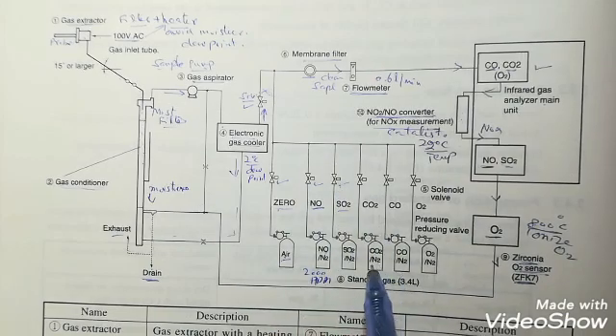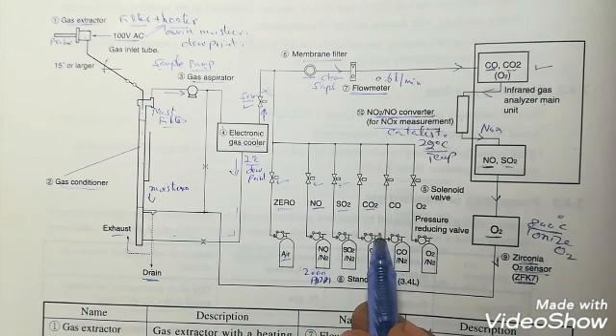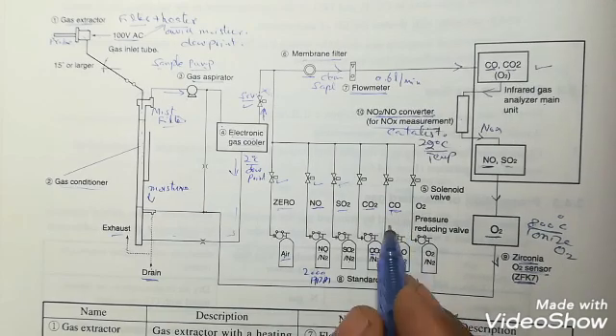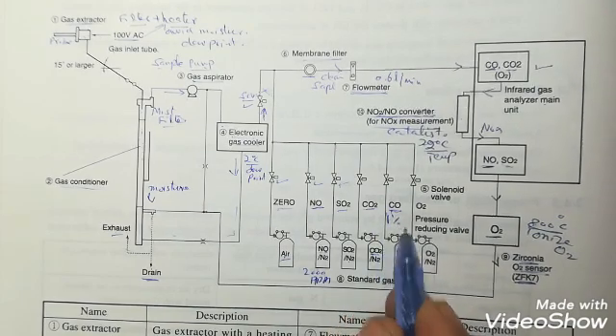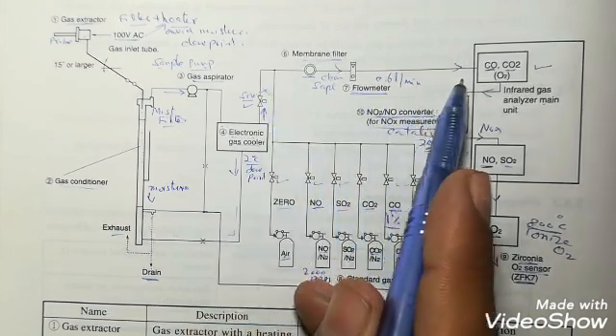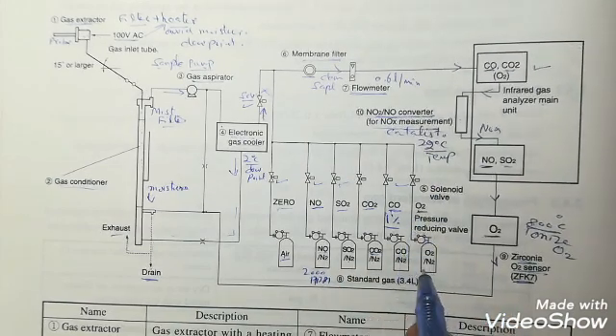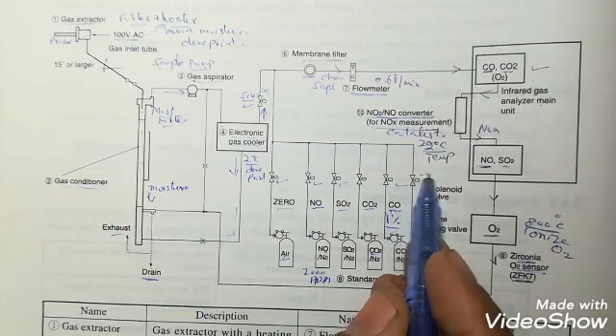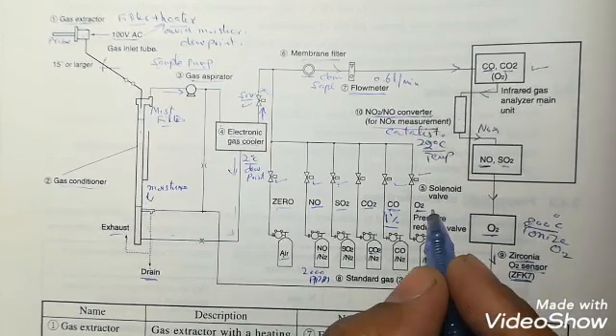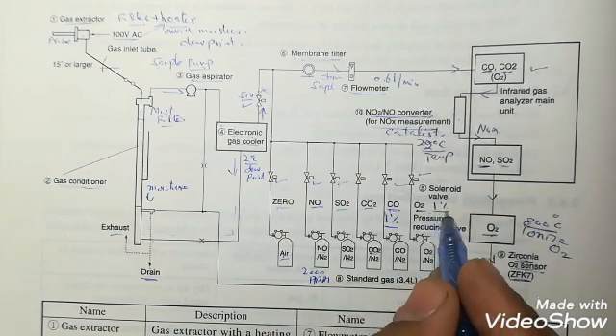The respective SOV will open and our gas reaches to the module. For the CO, the same SOV will open and gas is given. For the CO, we will use 1% of CO for the span calibration. For the oxygen span, we use 1% of oxygen in this Fuji model. For the ABB, we are using 21% for the span.